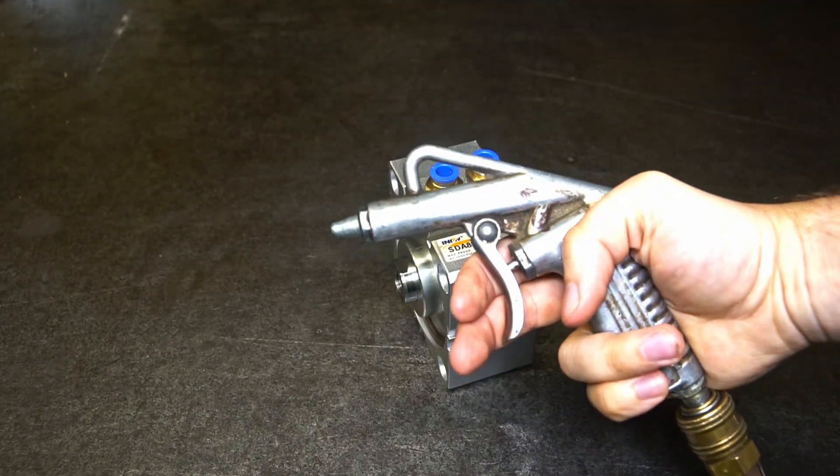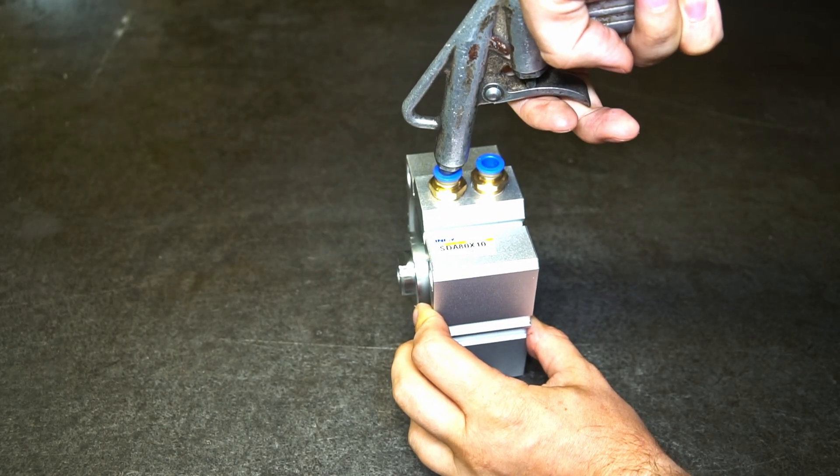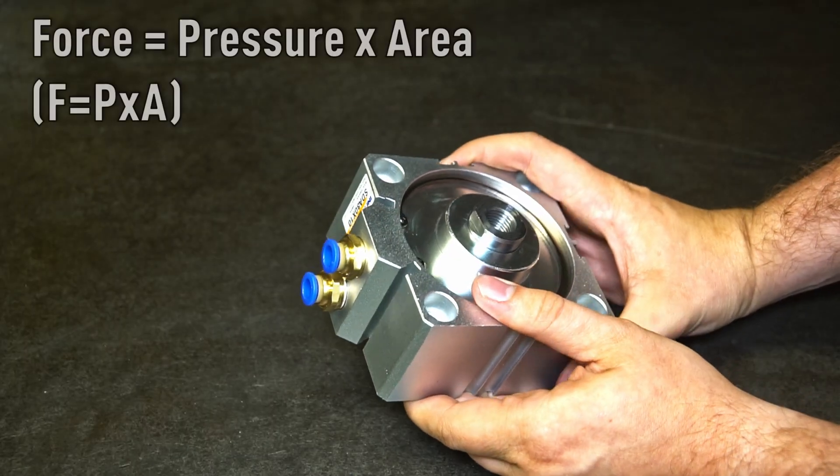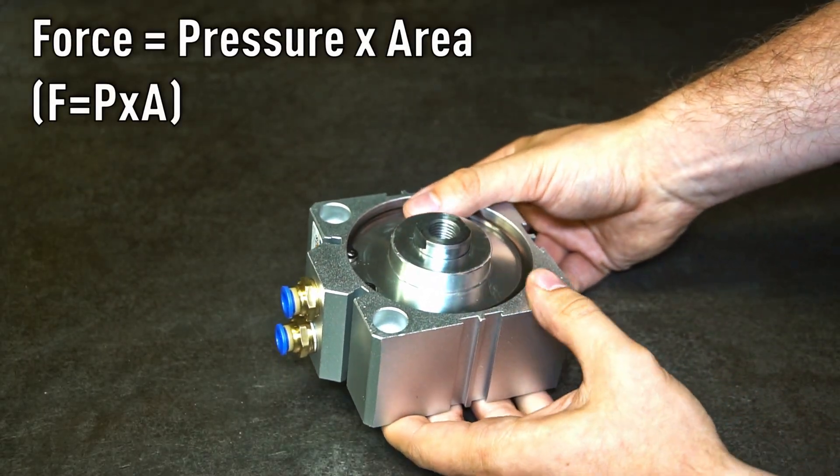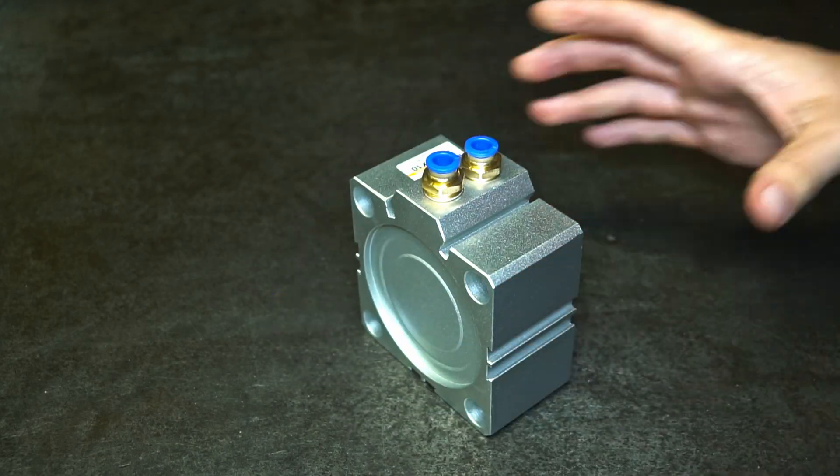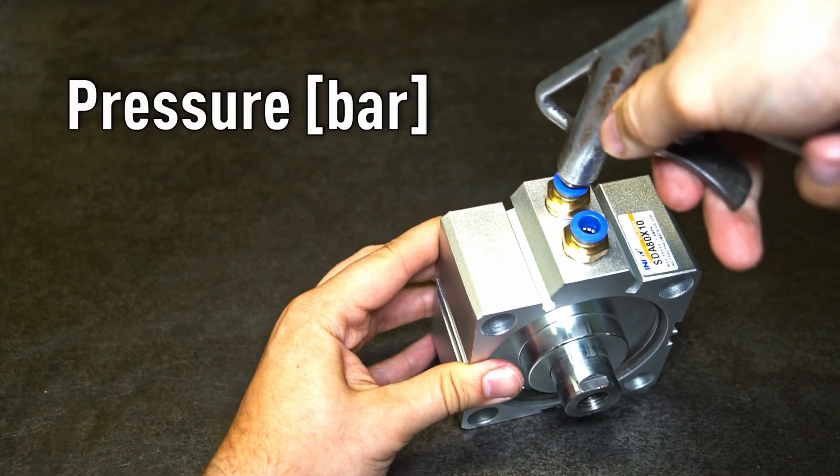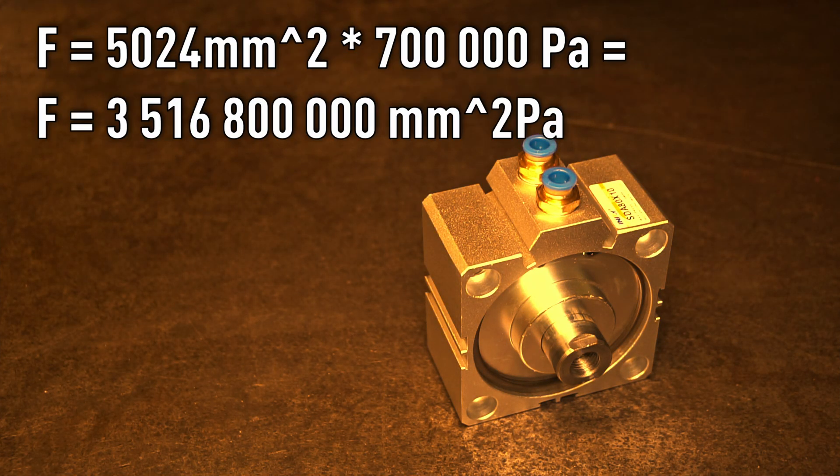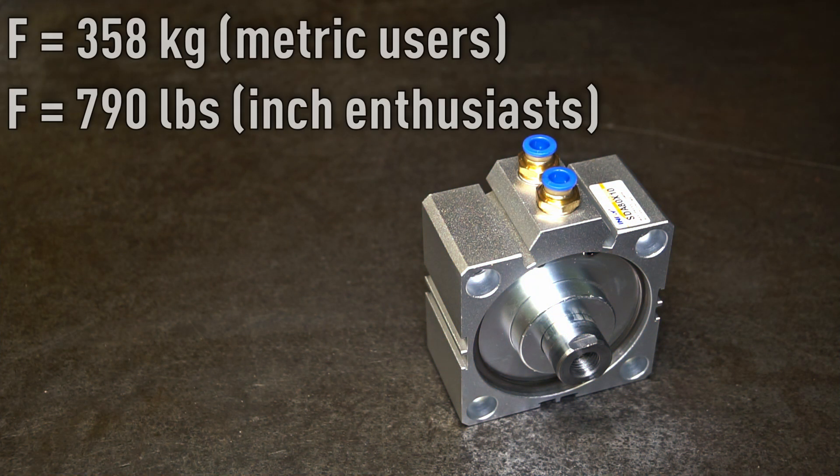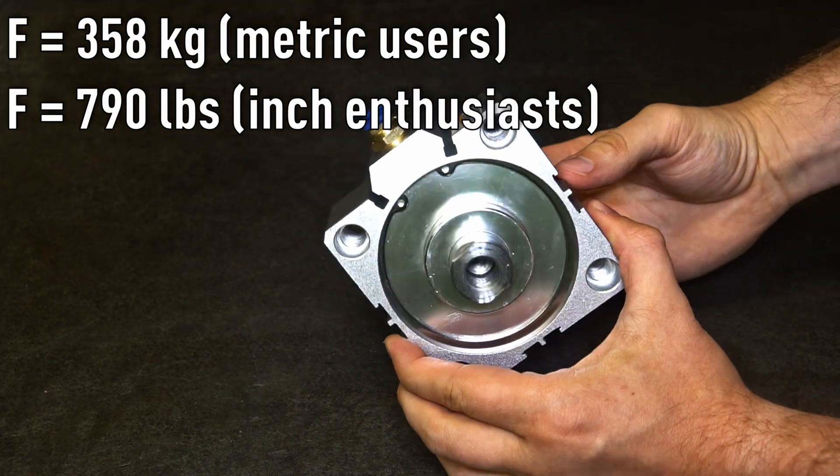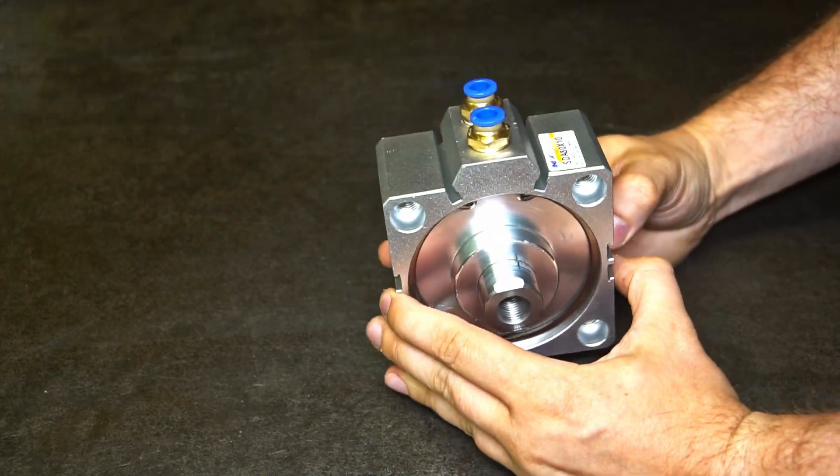Compressed air supplied to the right hole is used to force an air cylinder to move. Force equals pressure times the piston surface area. Area depends on piston diameter, which is constant for one air cylinder, and pressure, which depends on our supply. This particular one generates about 360 kilograms at 7 bar, which translates to 790 pounds for inch enthusiasts.